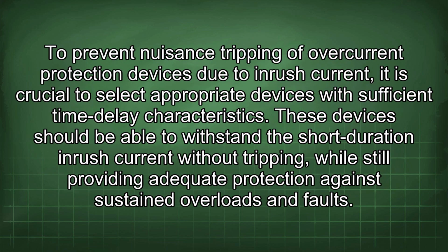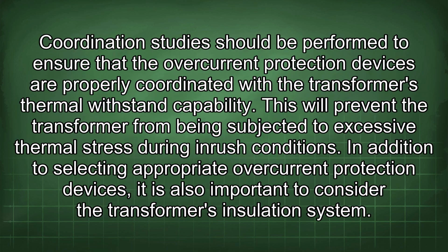To prevent nuisance tripping of overcurrent protection devices due to inrush current, it is crucial to select appropriate devices with sufficient time delay characteristics. These devices should be able to withstand the short-duration inrush current without tripping, while still providing adequate protection against sustained overloads and faults. Coordination studies should be performed to ensure that the overcurrent protection devices are properly coordinated with the transformer's thermal withstand capability. This will prevent the transformer from being subjected to excessive thermal stress during inrush conditions.